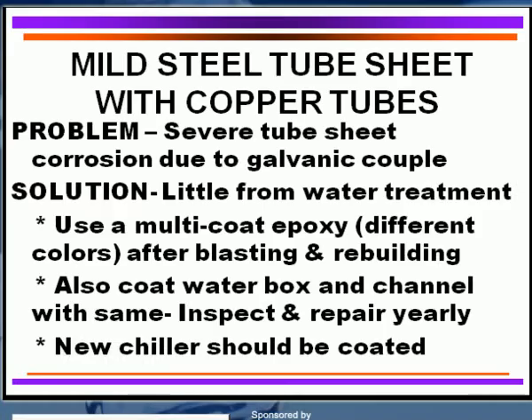So here's another area that we run into with heat exchangers, which is very common. The common aspect of it, of course, is that we're dealing with a mild steel tube sheet with copper tubes. How many people have this type of thing in their chillers? And then all of a sudden we have severe mild steel tube sheet corrosion due to this galvanic couple of copper and mild steel. This is a beautiful battery, where the copper will cause the mild steel corrosion to occur.